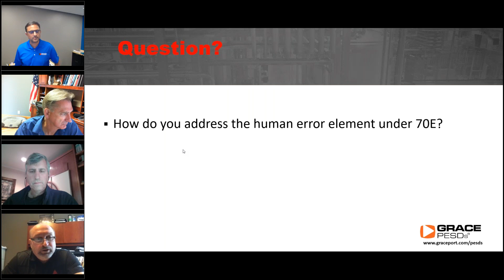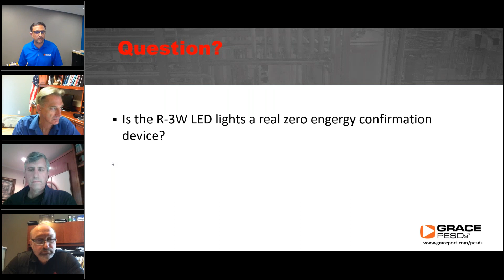Okay, thanks Terry. The next question is for me, this is product related. What we do here is the R3W LED lights, a real zero energy confirmation device. You can see the information on the handout provided. As far as the LED indicators, this cannot be used for verifying absence of voltage, we try to make this very clear. The LED indicators can only be used as part of a mechanical lockout tagout to visually verify voltage presence, intended for use by a task qualified person. In addition to the bump test, they can visually verify there is no energy present after they disconnect the switch. This does not mean measuring or performing a 3-point test, which is done with another product we make, a safe test point, which Charlie mentioned. You can look for more information or reach out to us to learn more about this device.